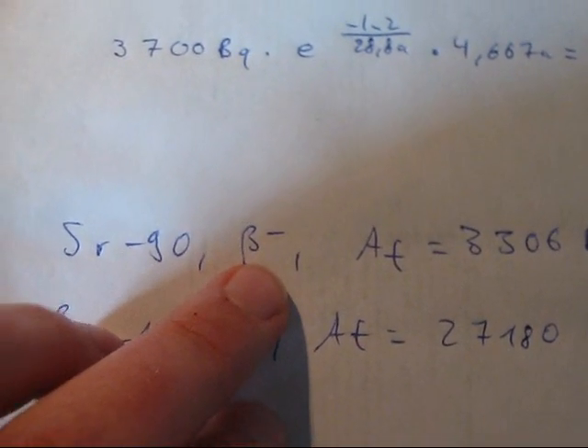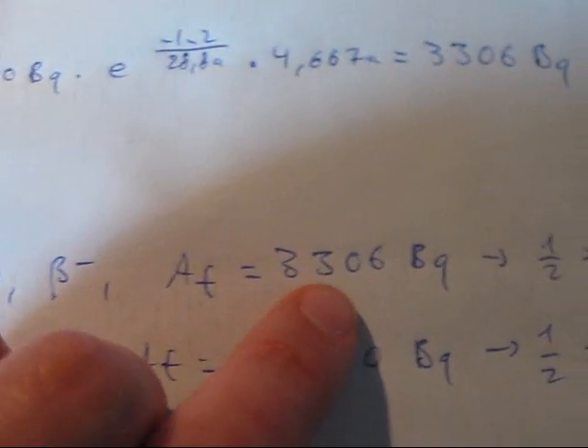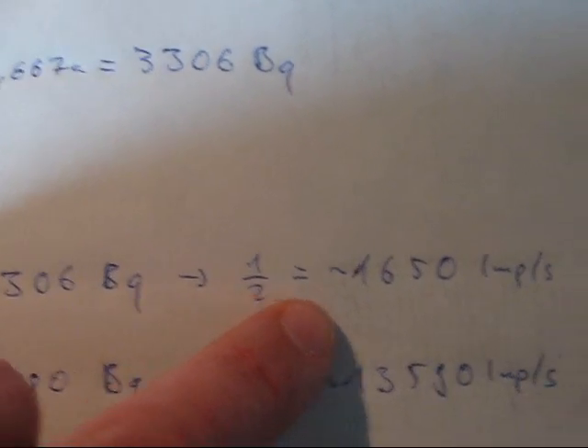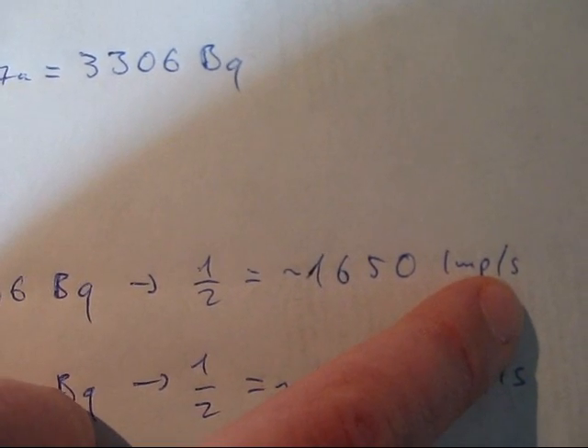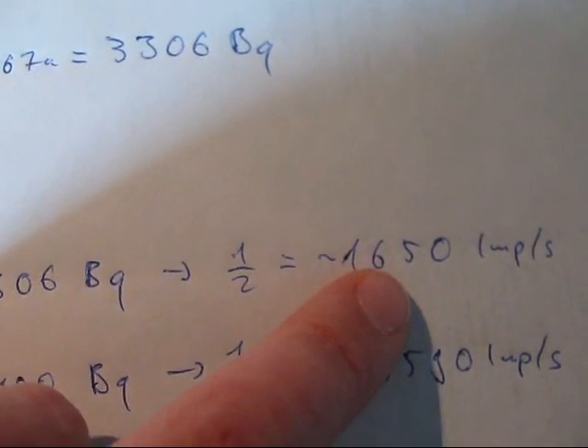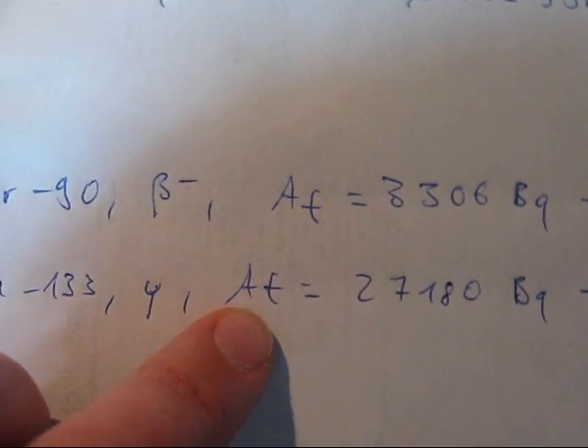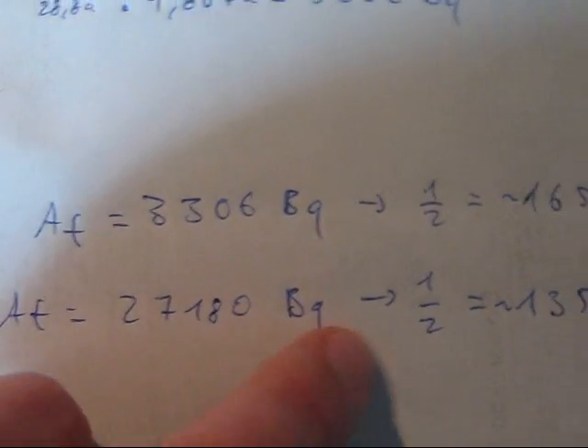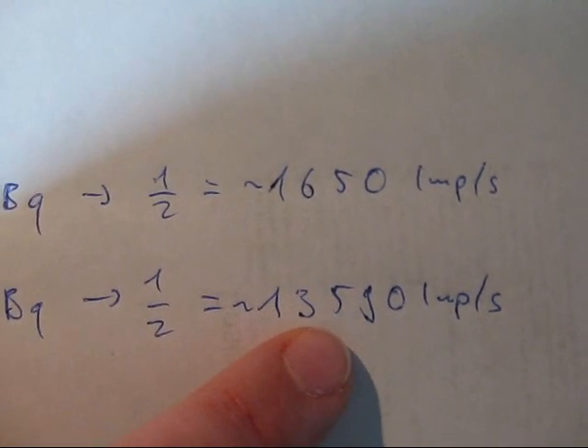For Strontium-90, which is a beta minus or electron emitter, we have a current activity of 3,306 Becquerel. Half of that, which we can estimate to be coming from one side of the source, would be 1,650 impulses per second, probably less than that, maybe around 1,500 or so. And Barium-133, which is a gamma emitter as it decays due to electron capture, has a current activity of 27,180 Becquerel, and half of that is around 13,590 impulses per second to be expected from one side of the source. It will be less than that.